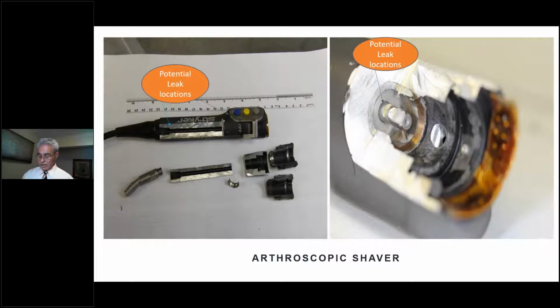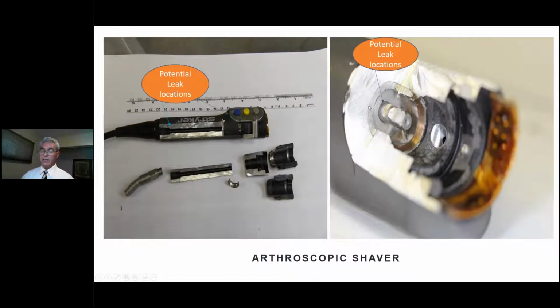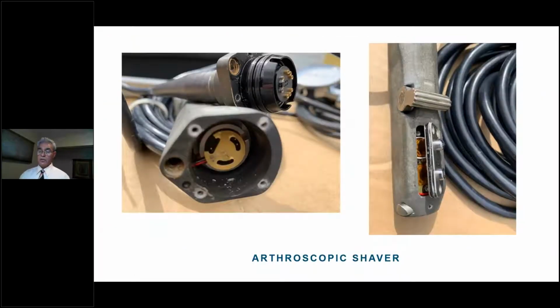The answer would be four or five different brush sizes and types to appropriately clean this shaver. Furthermore, which is not included in the IFU—I haven't seen any IFU mention this—there's a potential, because of the O-rings, for leaks to go inside the shaver's mechanism, get hot, and let debris and bioburden inside. So if you don't want to cut one open, you can use an Allen wrench to open some of these.